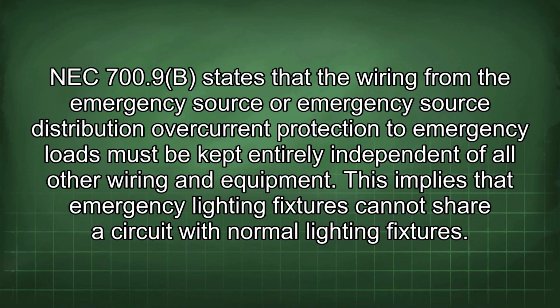NEC 700.9(B) states that the wiring from the emergency source or emergency source distribution overcurrent protection to emergency loads must be kept entirely independent of all other wiring and equipment. This implies that emergency lighting fixtures cannot share a circuit with normal lighting fixtures.